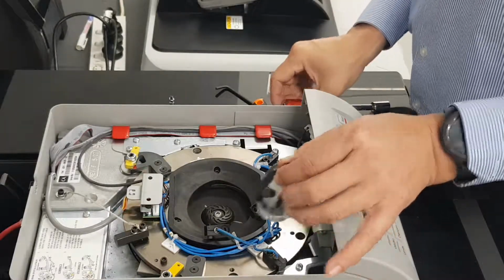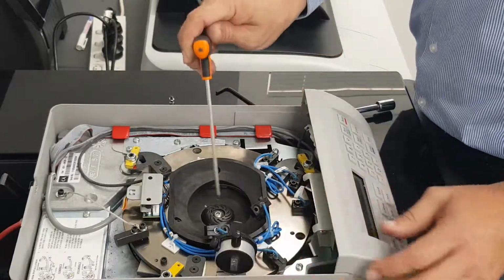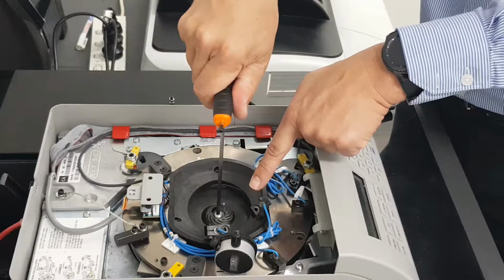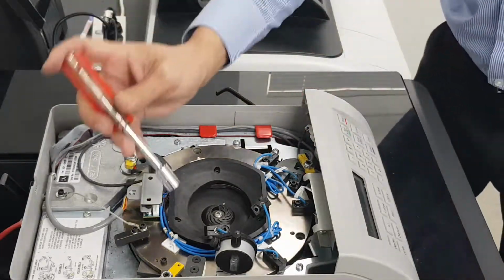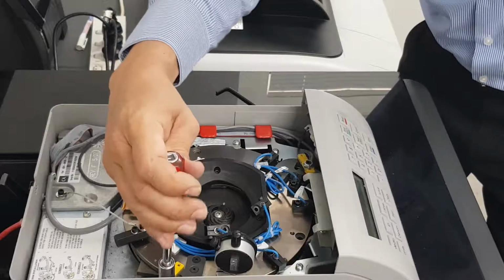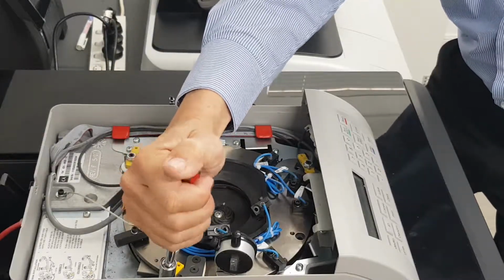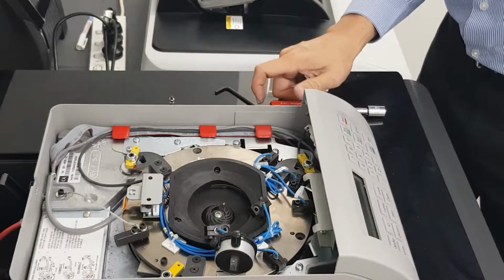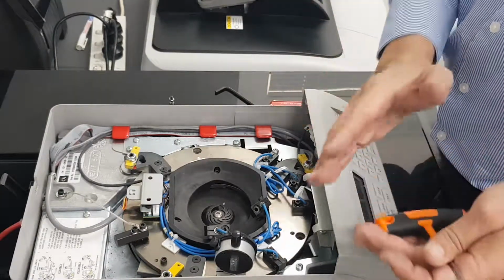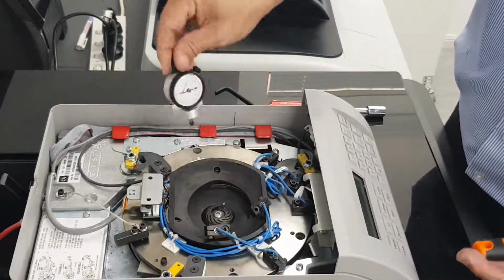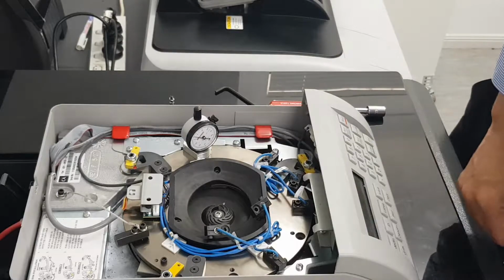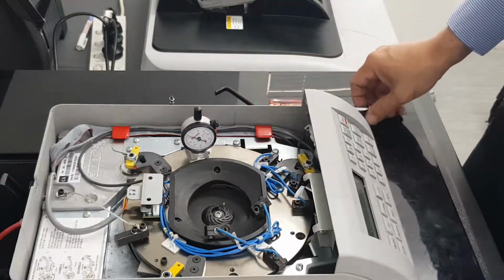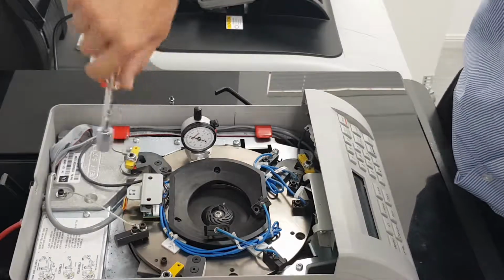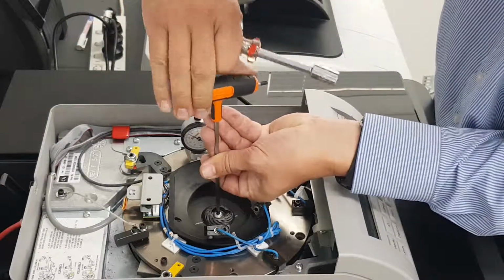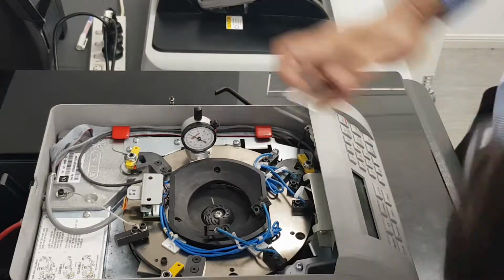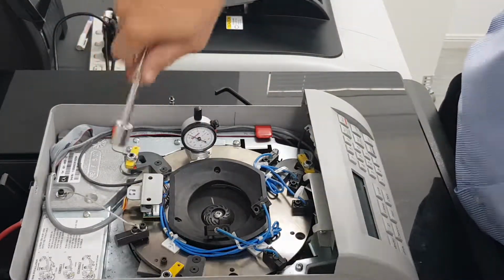Pretty good. And we move around to our last point. And again, just make sure that high point on the mat lines up. It's probably about 0.005, so I'll just give that a bit of a tweak. Okay. Excellent. And you'll find that when you adjust each one, it can throw the other point out a little bit. So I always go around at least a couple of times just to make sure. Yeah, it's throwing that one out a little bit, so I might need to just tweak that and adjust the high point around. It's actually not too bad now, I've done that.